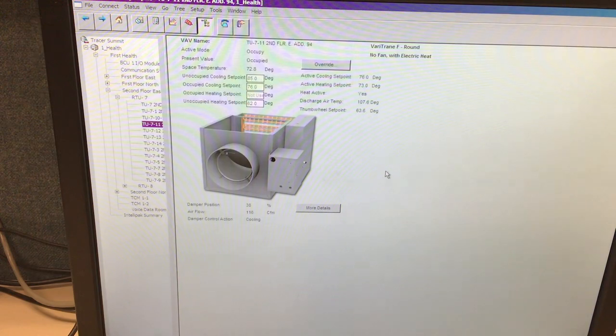Okay, we've picked up, what, half a degree with the heat being on. So somebody out there is probably noticing, well, all of a sudden I'm starting to get a little warmer. Less than a degree, so they probably just feel the warm air blowing. It hasn't changed temperature in the room that much. So say, okay, maybe I got the wrong VAV. Let's say that I did, or they really don't want to be 76 degrees. Let's put it back to 75.